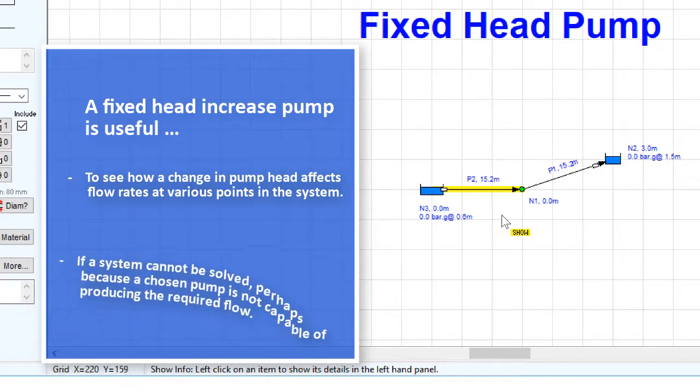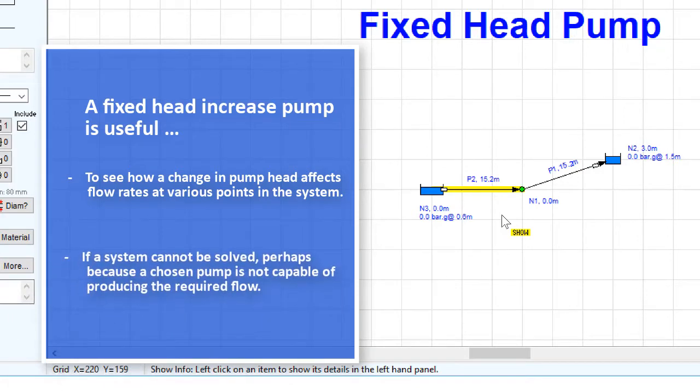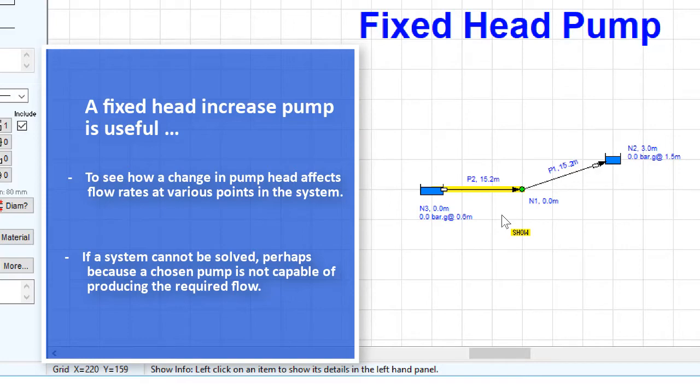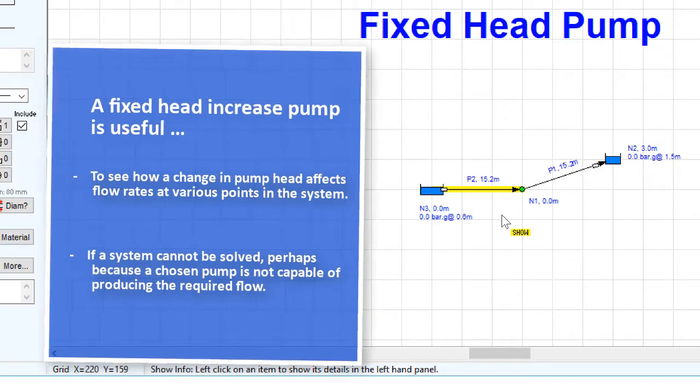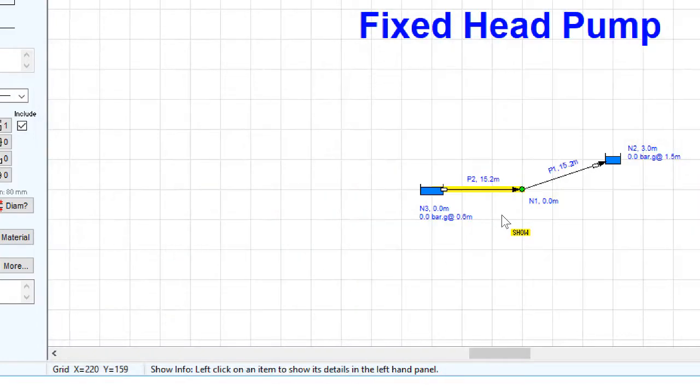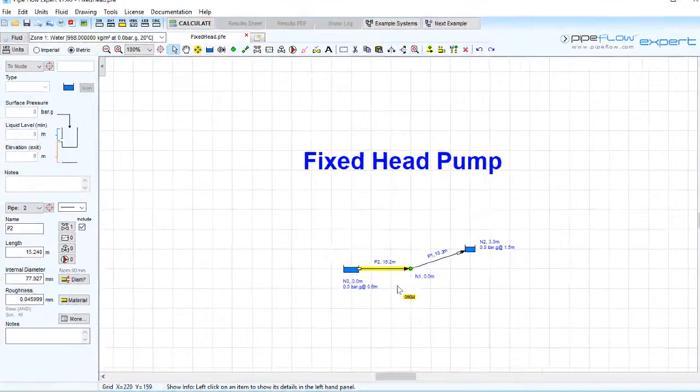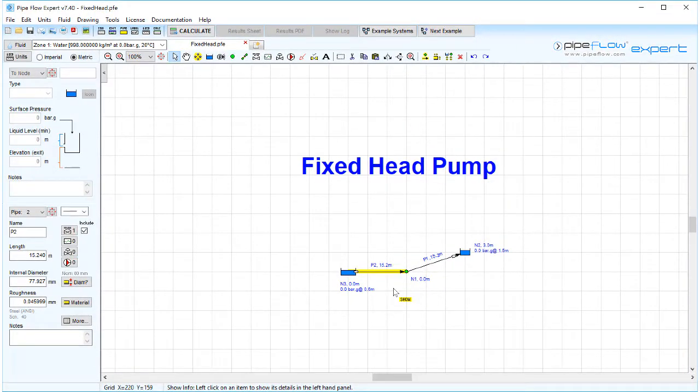This modeling tool can become particularly useful when facing difficulties in solving a system. You can solve a system using a fixed head pump that adds a high pressure which can then be progressively reduced and the system resolved. This will identify the minimum pressure needed to produce the required flow through the system.